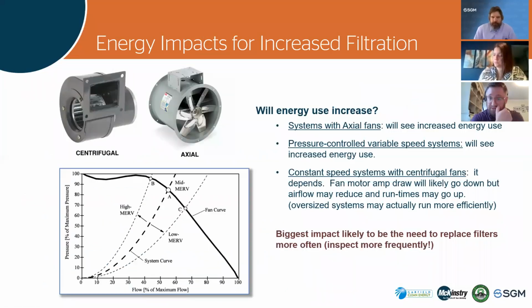Yeah, so I'm actually going to speak to some of those energy impacts. It's interesting. It's not as cut and dry as you'd think. So what we're doing is adding pressure drop to the system. Systems with axial fans, these will see increased energy use and a drop in airflow likely. Anything pressure controlled, it's likely that it can keep up, it can compensate for that increased pressure drop, but it's going to increase your fan energy use.